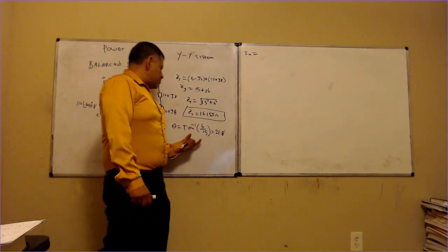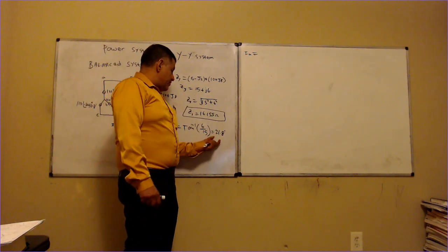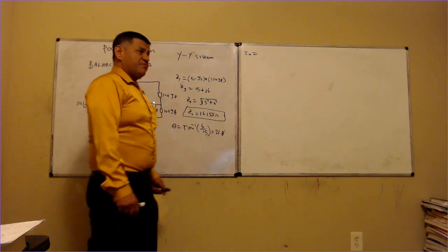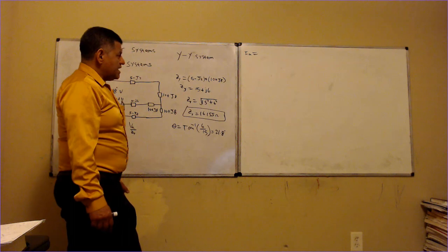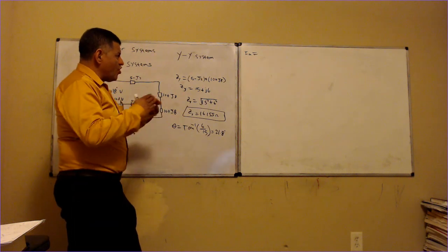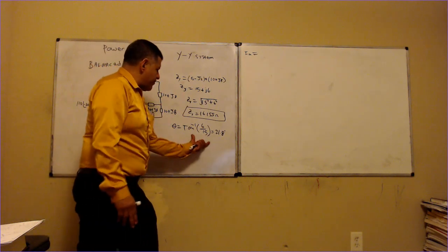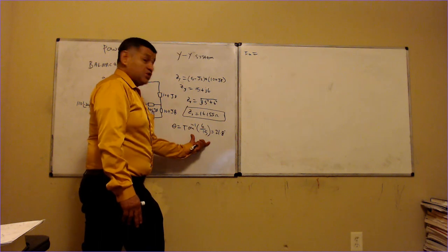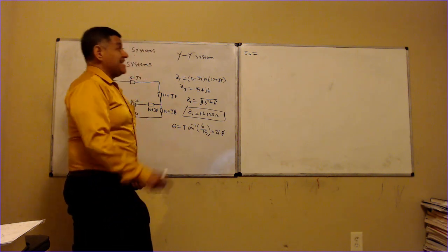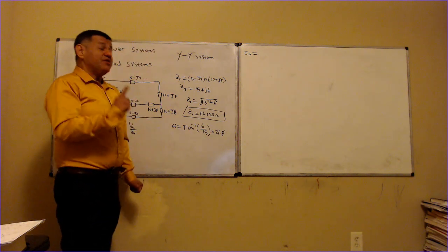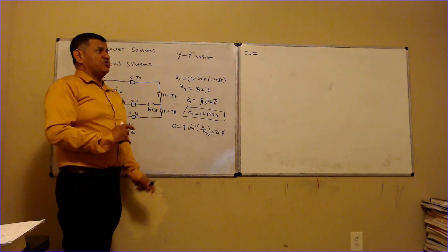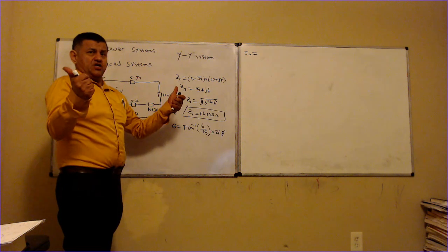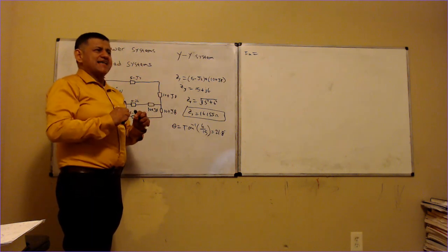But in the other case, it was imbalanced. If I have more circuits in one phase, one of the three phases, it does not matter. And let me restate this. People think sometimes that just because you have a three phase system, you can count that as a single node.